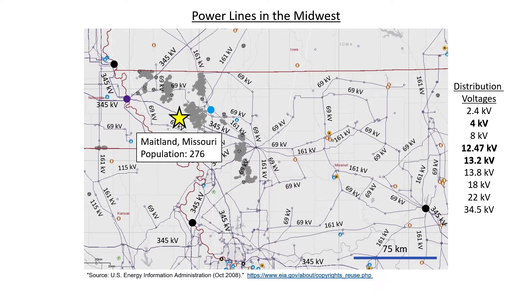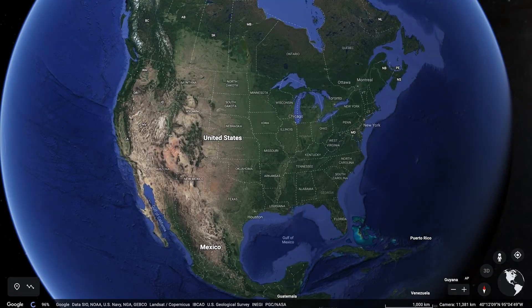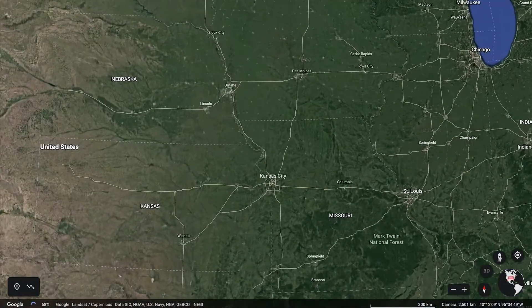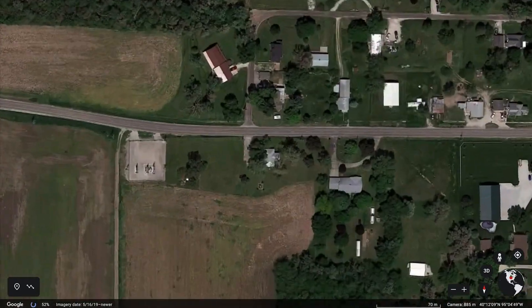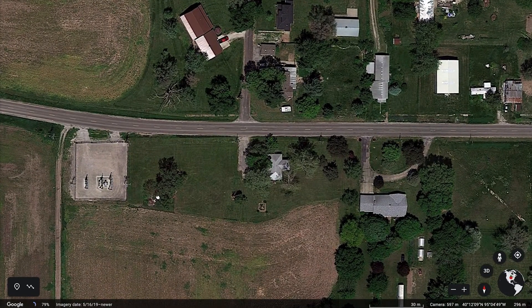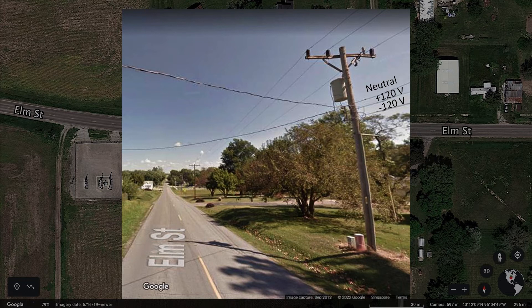Now we're going to see where a town's electricity comes from. Let's start with a map of the United States and zoom into the little town of Maitland, Missouri. We're going to start with the last power lines that are on the secondary side of this pole transformer on Elm Street. This neutral and plus and minus 120 volts would be delivered directly to a house or a group of houses. The primary side of this pole transformer is connected to one of three phases, each at 12.47 kilovolts — one of the most common final distribution voltages in this region.